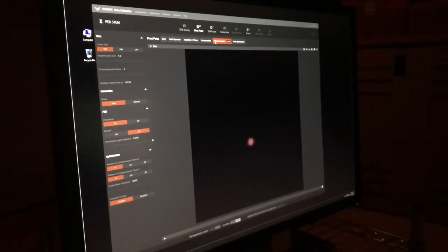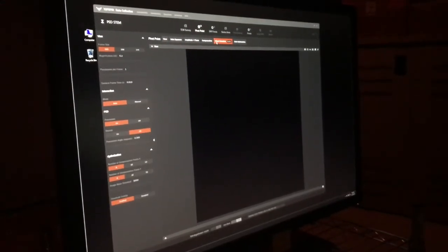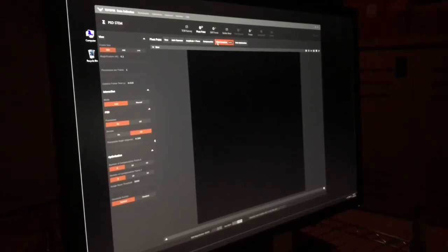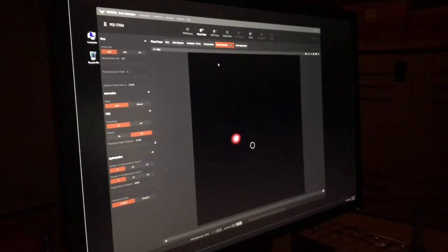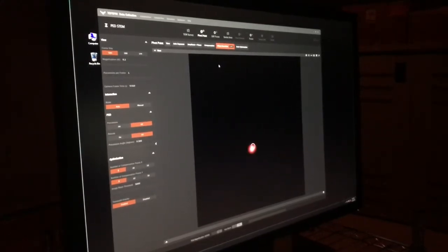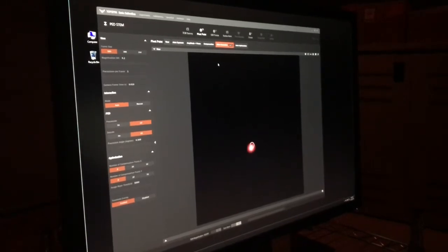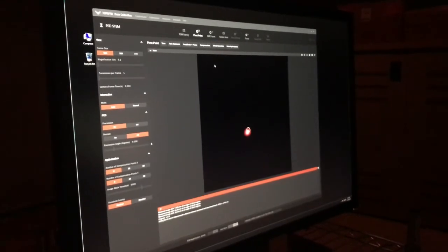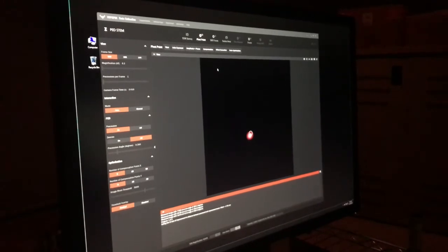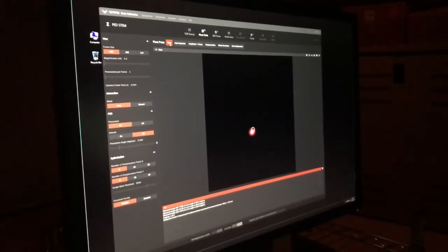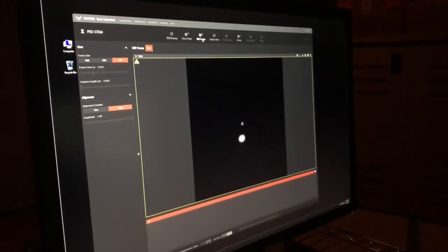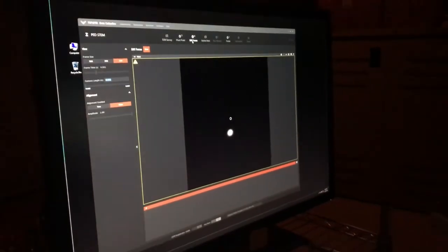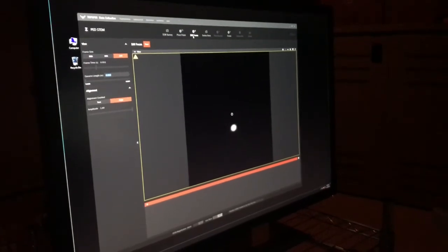To make sure the beam position is not severely affected by precession, we click on the offset correction. In this case, we don't have to manually stop it. The computer will tell us when it's corrected. Moving to step 3, diffraction focus. Center the beam using the trackball.